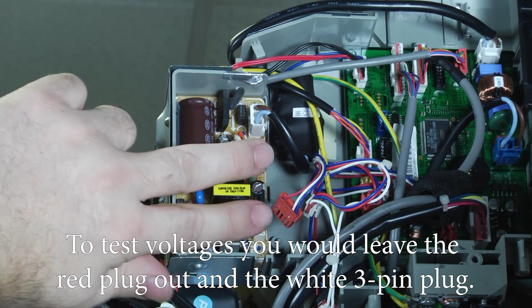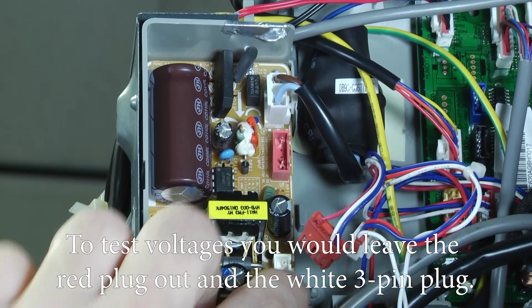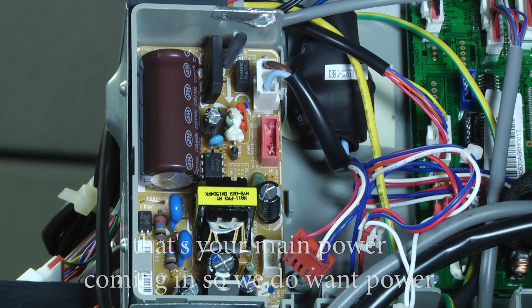Let me get everything back in place. Okay, we've got the board in place. To test voltages, you would leave the red plug out and the white 3-pin plug, but leave your white plug with the blue and brown wire, that's your main power coming in. So we do want power to go through this board, but we're going to measure DC volts coming out to verify it's the correct voltage.